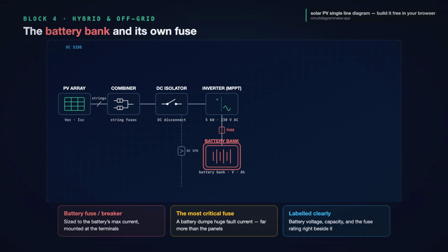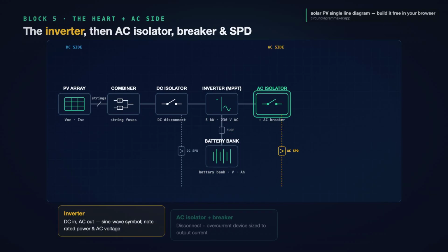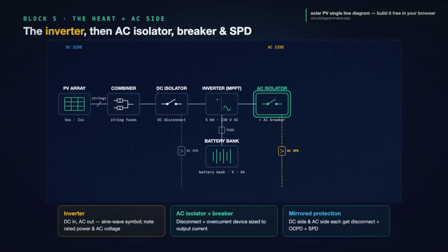So on the single line diagram, it is drawn big and labeled clearly, battery bank, its voltage and capacity, and the fuse or breaker rating right beside it. Block 5, the inverter and the AC protection on its output. The inverter is the heart of the drawing, DC in on one side, AC out on the other, shown with that little sine wave symbol inside a box. Next to it, you note its rated power and its AC voltage.